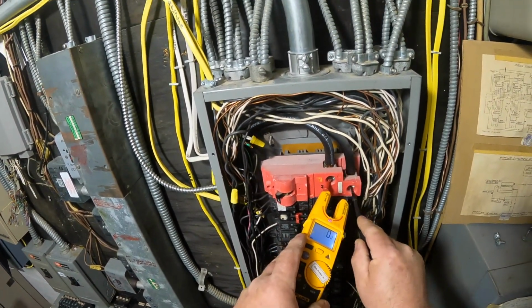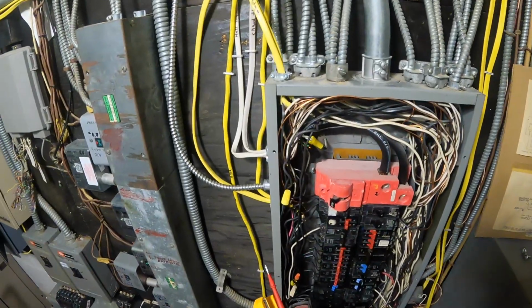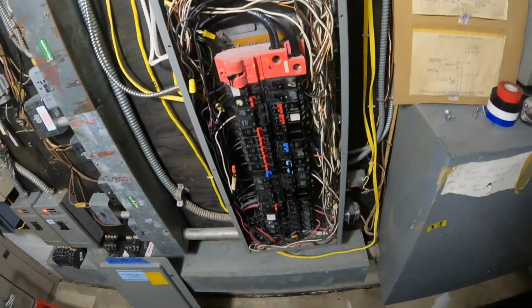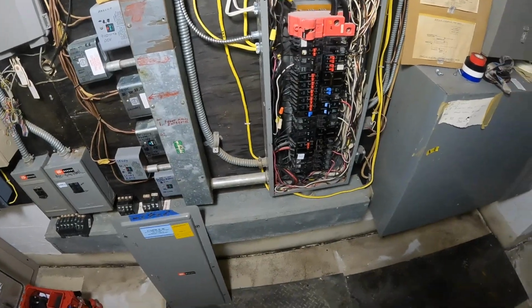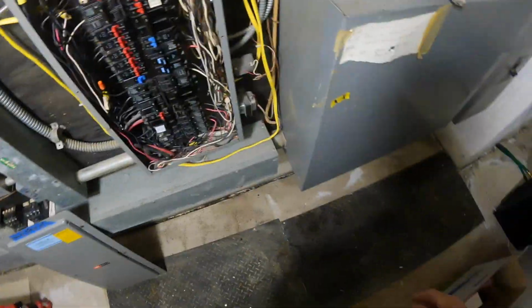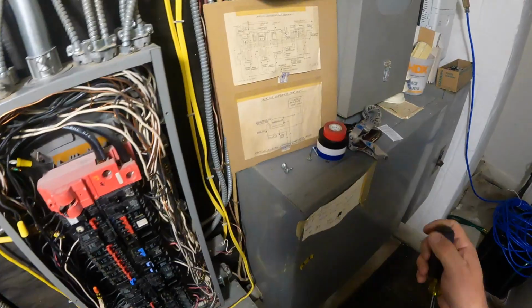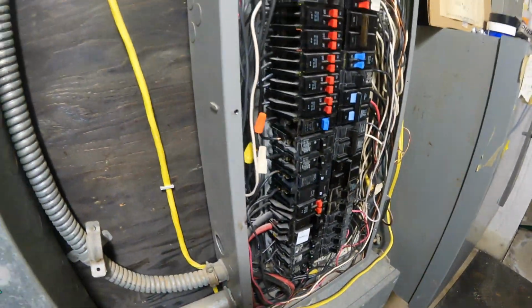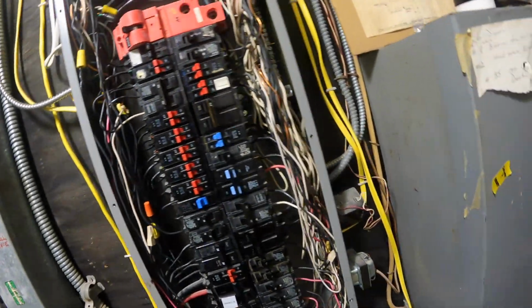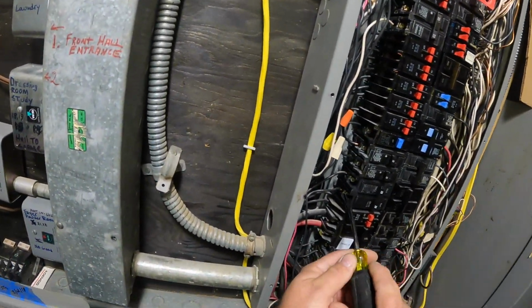Now that conduit up on the top there feeds another sub panel over there to the left. I believe it was 100 amps. I doubt highly that it was ever inspected just because of the workmanship of that conduit. But I wasn't there to upgrade that. I was just trying to make this panel safer without more circuits than was rated for the panel. That's always an important thing.